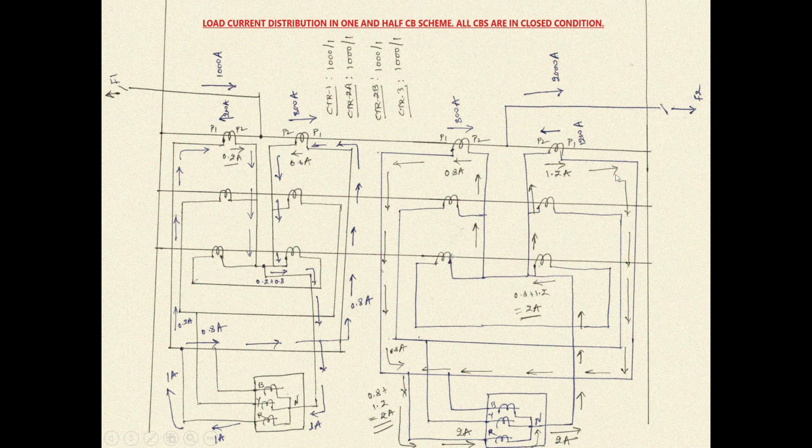The importance of this current direction actually comes into the picture in both measurement and protection. If the current direction is not proper, then your relay, or the measuring device, might see import of power as an export, and your metering will not be proper. Another factor for this improper direction comes for your directional relay.